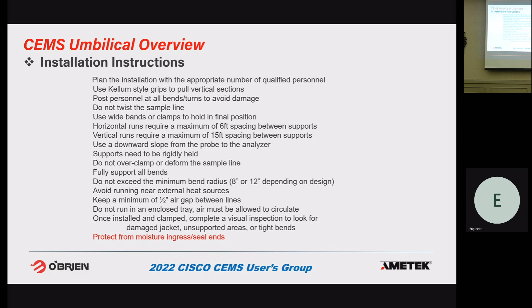Once it's installed and clamped, do a good visual inspection. It's not uncommon during installation that the jacket gets cut, goes around a bend, hits a piece of unistrut or something. As long as it hasn't rained and you address it quickly, it can be repaired and it doesn't hurt the bundle at all.